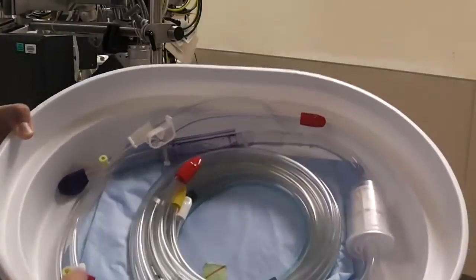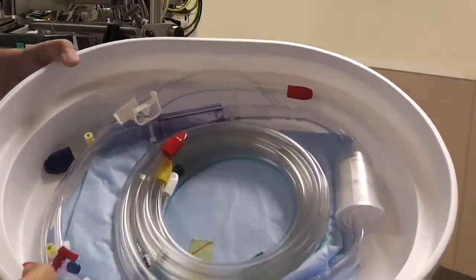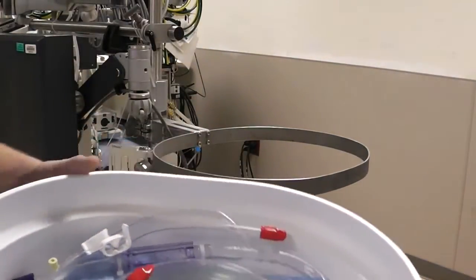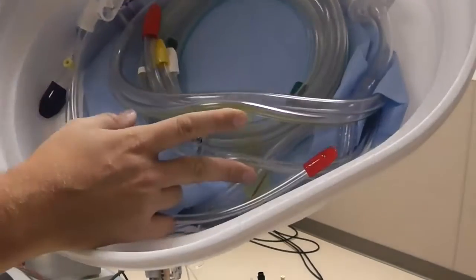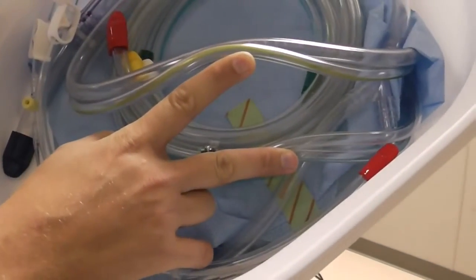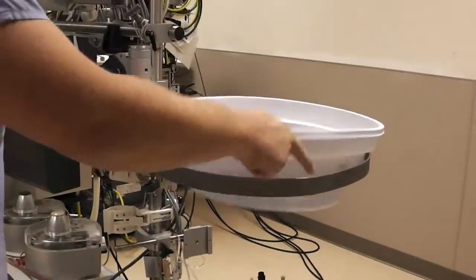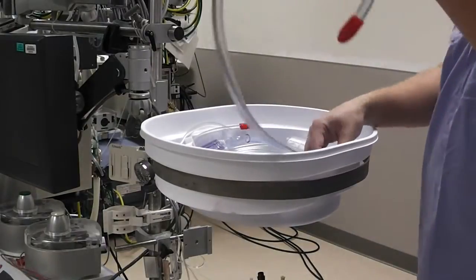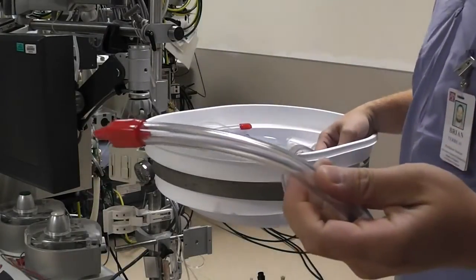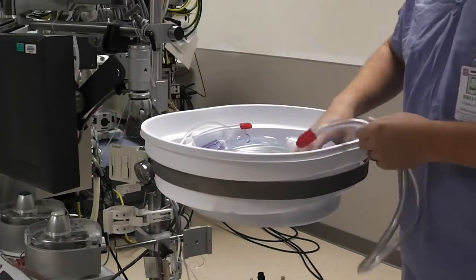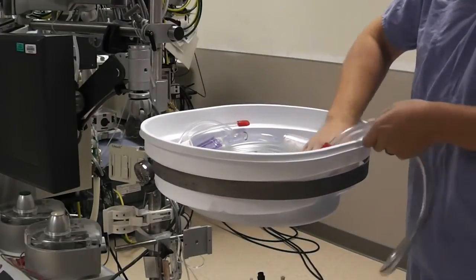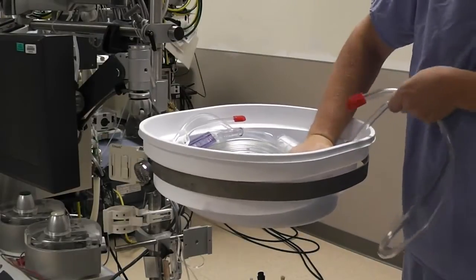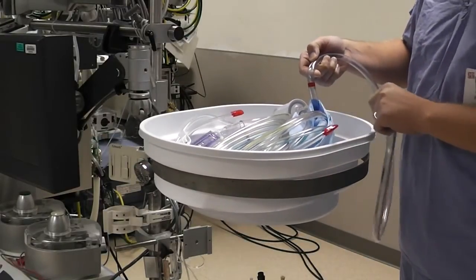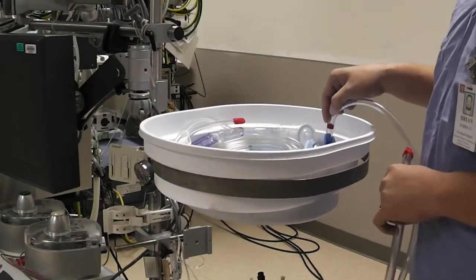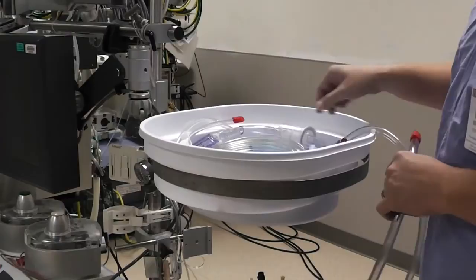Next, you're going to grab your bucket full of all your lines, and you're going to place it in the basket holder here with the tape side. Hopefully you can see that, but there's a green tape in there away from the pump. Set it in here like that. And you're going to take your arterial line, which is the one with the red cap on it, and you're going to pull it out of the paper in here until you see the red tape on the line. Now everything past that tape is sterile, so it has to remain inside that paper.